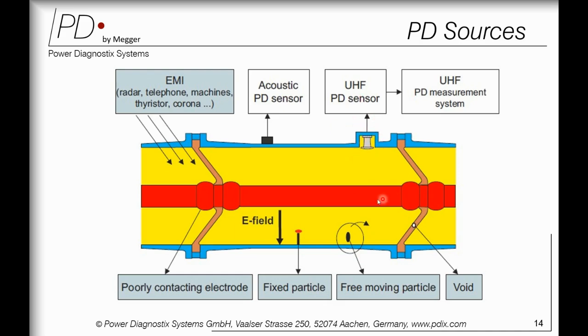Normally you have UHF sensors, because whenever there is a PD, it will create electromagnetic waves, and those waves will travel from your PD source to your UHF sensors. Another is acoustic, which helps you pinpoint where it is, using piezoelectric sensors. Also, sometimes you might have high noise due to EMI, that means telephones, machines, radar, thyristors, which typically work at very high frequency, from 200 megahertz to 2000 megahertz. Any types of impurities like poor contact, sharp edges, moving electrodes, surface discharge, voids, can easily be captured using the UHF, and later you can use the acoustic to pinpoint where it is.